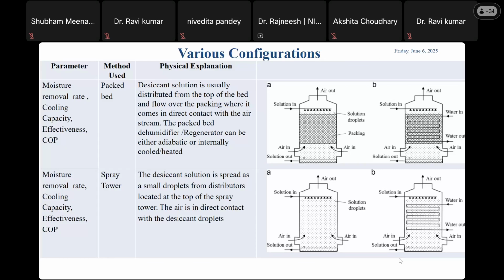The desiccant solution is usually distributed from the top of the bed and flows over the packing, where it comes in direct contact with the air. This is similar to the desiccant wheel concept.